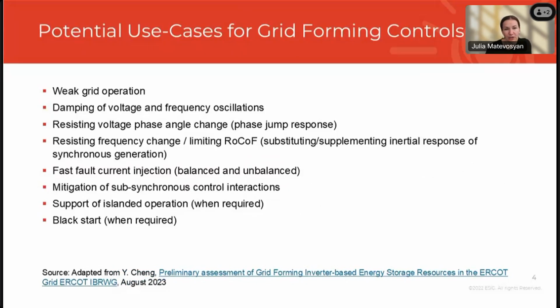So potential use cases for grid forming controls are to support weak grid operation, so that grid following resources in weak grid areas can continue operating stably. Provide damping of voltage and frequency oscillations, resisting voltage phase angle change, sometimes called phase jump response, and resisting frequency change or limiting rate of change of frequency. This is viewed as a substitute or supplement to the inertial response that is provided by synchronous generators today.